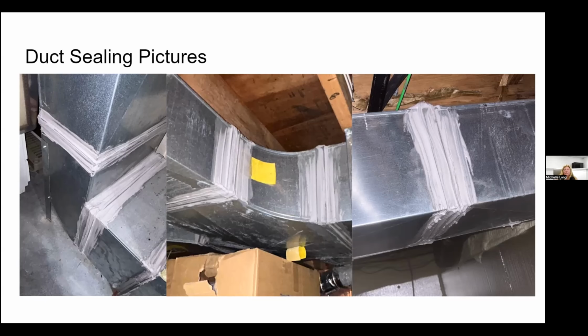It's an AeroSeal product. I don't have notes on a slide for this, but it's kind of like when you get insulation done — it'd be an add-on measure. There's a rebate for it, $1,000 per system... well, I always say it's only $1,000 right now. Someone comes in and does the AeroSeal product, sealing the ductwork from the inside. We recommend this when you've got a lot of ductwork going up walls, in places we can't get to seal from the exterior.